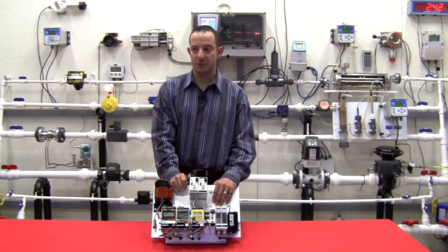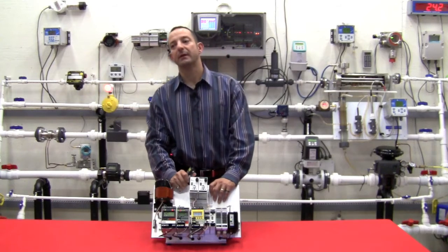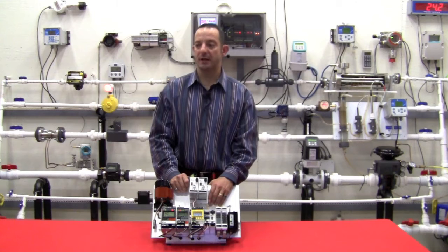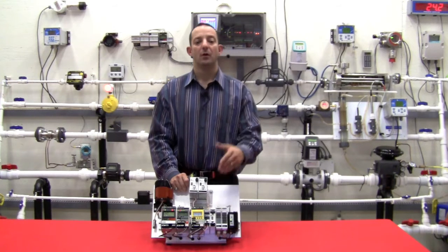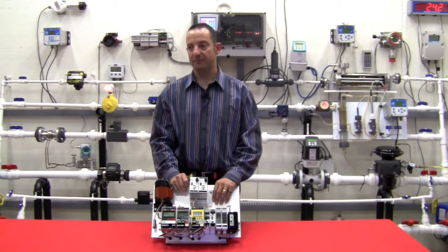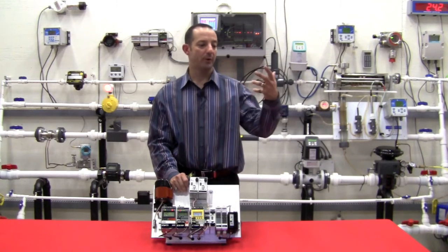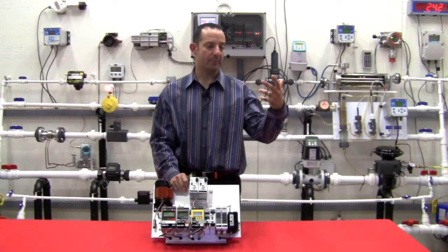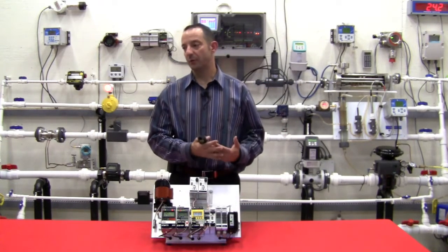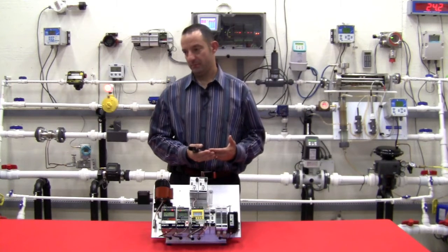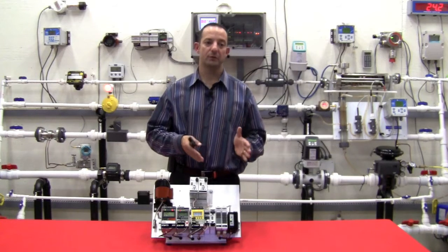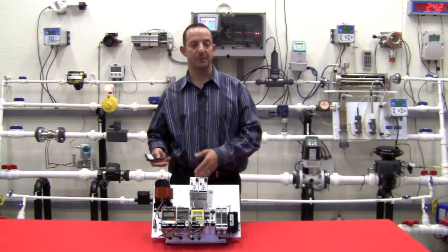The second application you want to mention is signal splitting, and this is becoming more popular with gas companies who share transmitters for measurement purposes and control purposes. Often the compressor automation group will want to read a pipeline pressure from a control standpoint, but then the measurement group also wants that transmitter's signal because that signal is also needed by the measurement system.